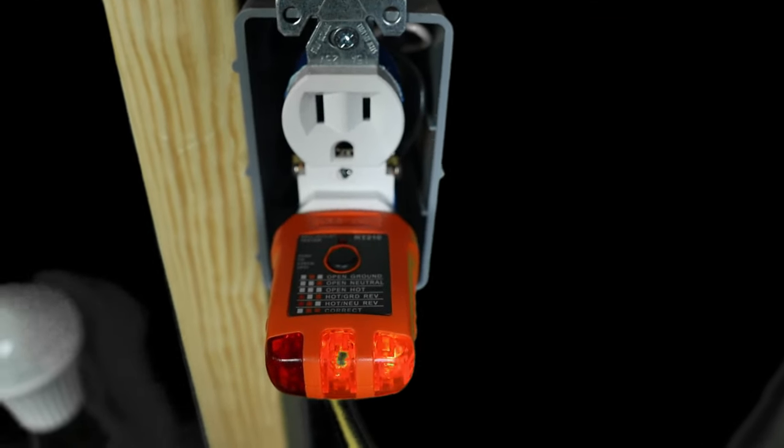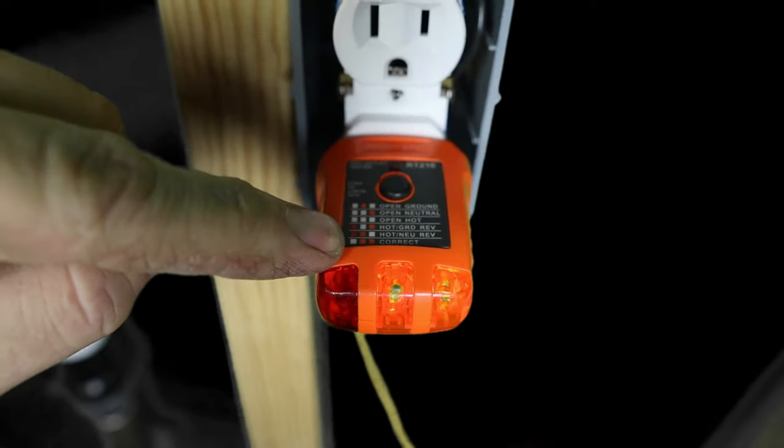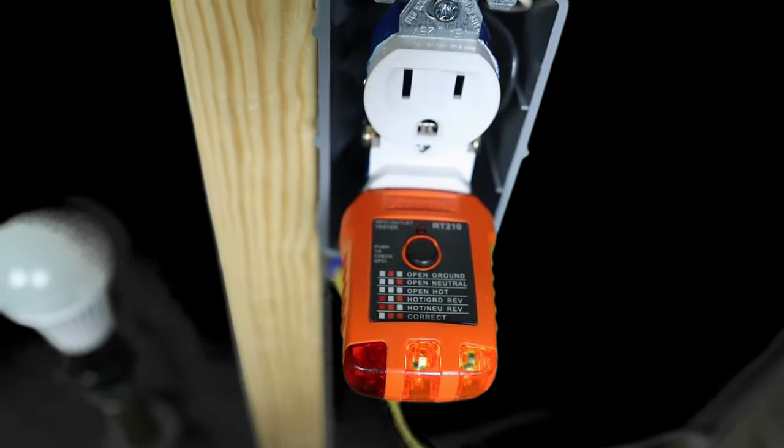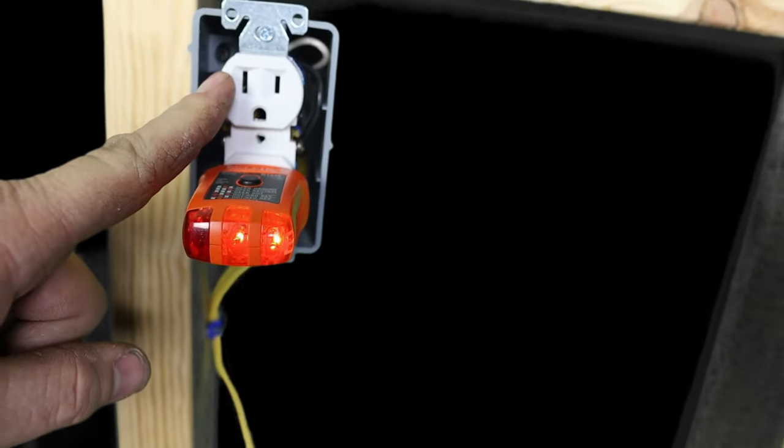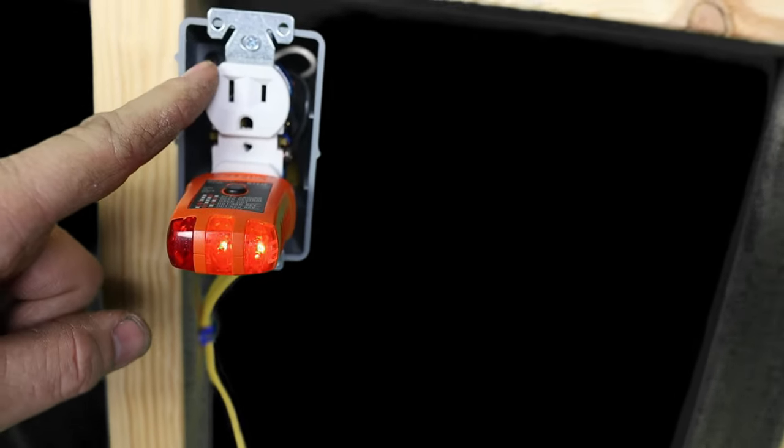So let me show you what he did. So you can see right here that both of the lights are lit up now, which if you look here, which you probably won't be able to see or maybe you can, it says correct. But it's the same receptacle. So what did he do? Well, let's take it apart and look.